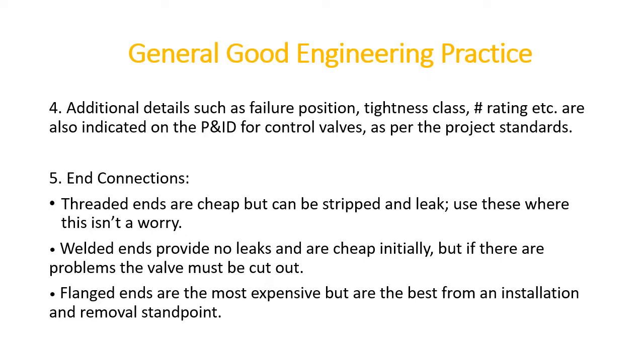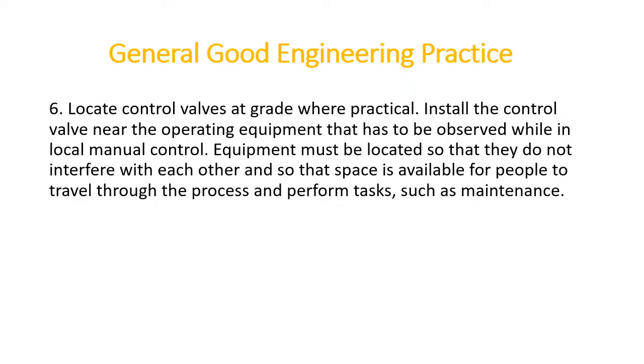And now the fifth point, end connection. Threaded ends are cheap but can be stripped and leak. Use them where this is not a worry. Welded ends provide no leaks and are cheap initially, but if there are problems, they must be cut out. Flange ends are the most expensive, but are the most common type from the installation standpoint.